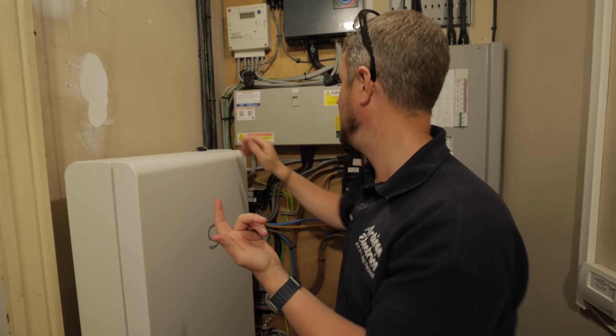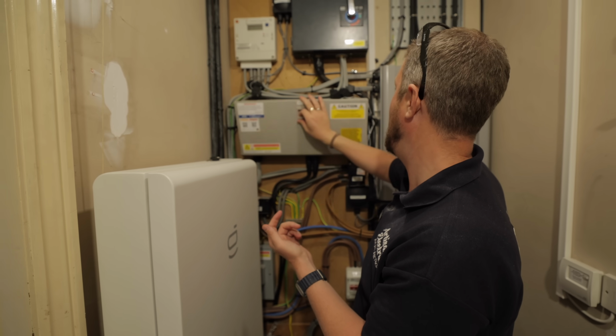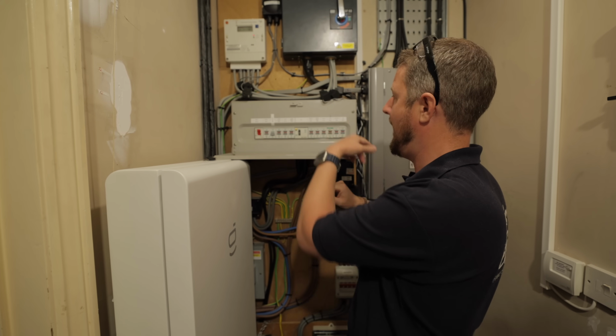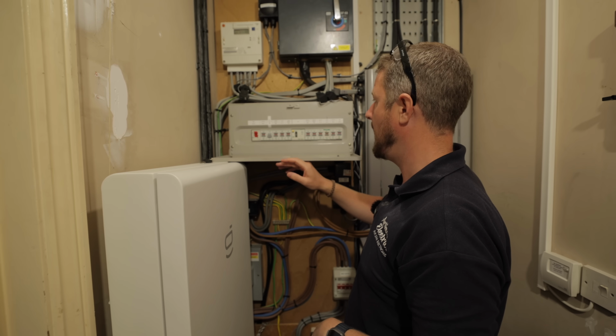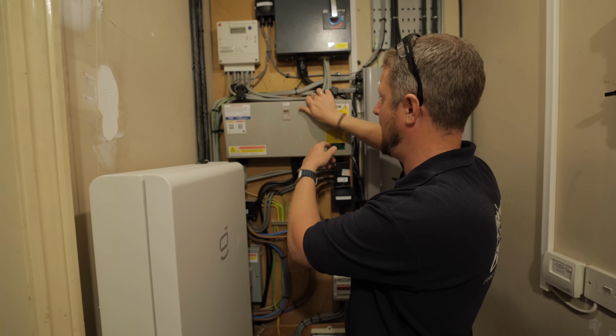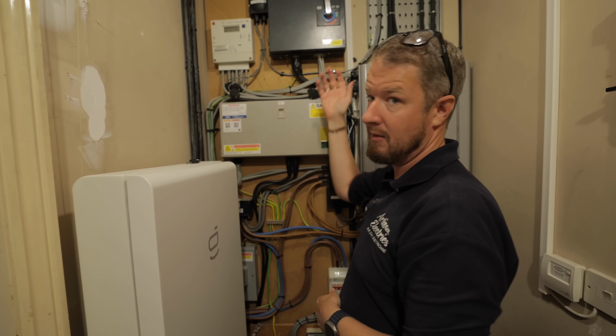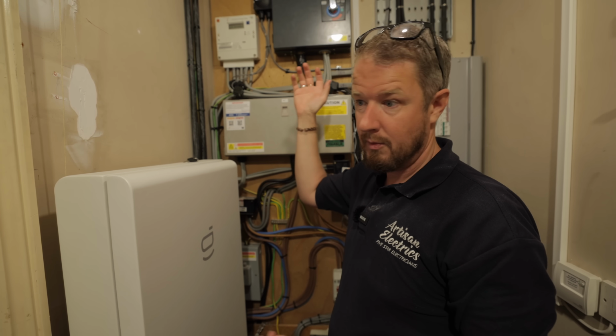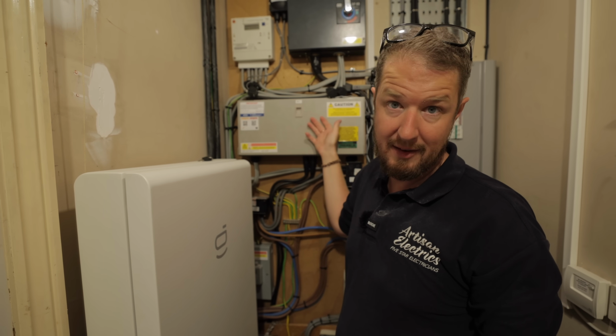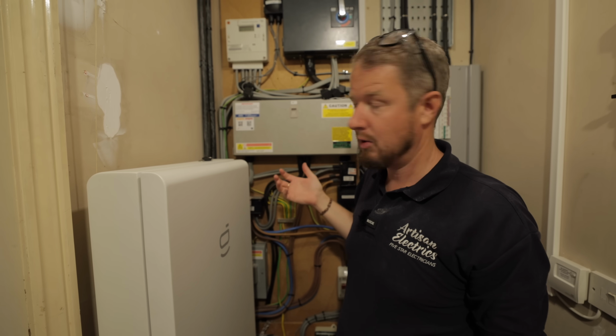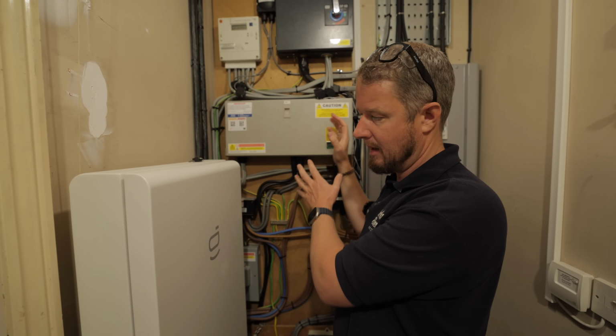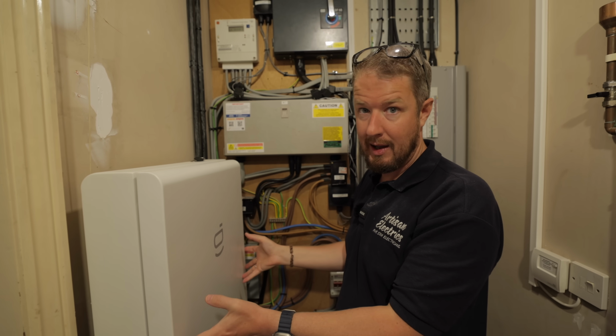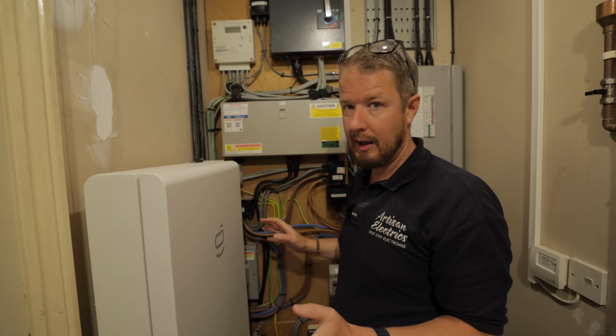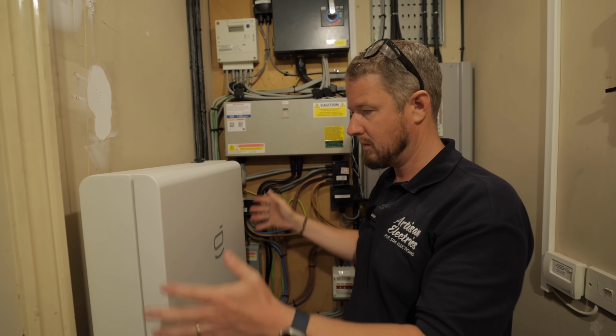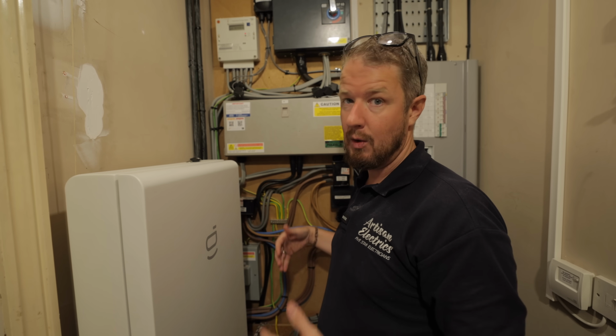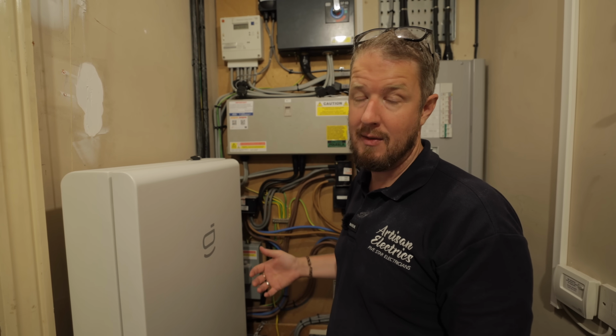For example, if I'm an electrician working on this property and I want to shut down the power, the consumer unit, to work on it, but there's a solar circuit connected into this, if the inverter didn't shut down when I turn the power off, what's going to happen is this board is still being fed from the inverter and I could get an electric shock. So that's the reason that normal inverters without a gateway like this will not work in an off-grid situation. We always need to install some kind of backup gateway in order to be able to have off-grid power in the event of a power cut.